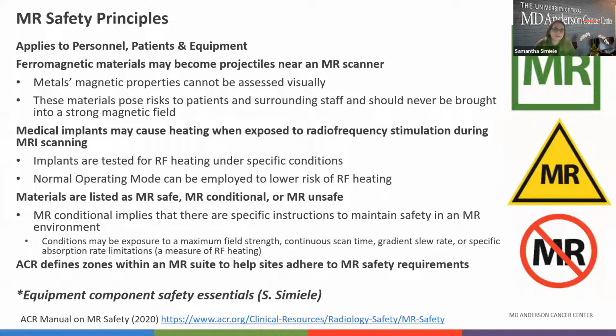Thank you. I'm just going to make a couple of quick comments about our applicators. We have developed a very robust process for making sure what we are bringing into this OR suite is safe for both the patient as well as our staff. One of the first things we do before we consider using any type of applicator in the MR space is we review the IFU. And we don't just review this within our team, we also reach out to our collaborators in imaging physics and they review this IFU with us. We are reviewing the stated materials included in the applicator components. We're also looking at what testing the vendor did for this equipment to state that it's MR compatible. We're looking at the magnet strength they performed their testing under, as well as any other conditions stated. If we have any questions, we contact the vendor.